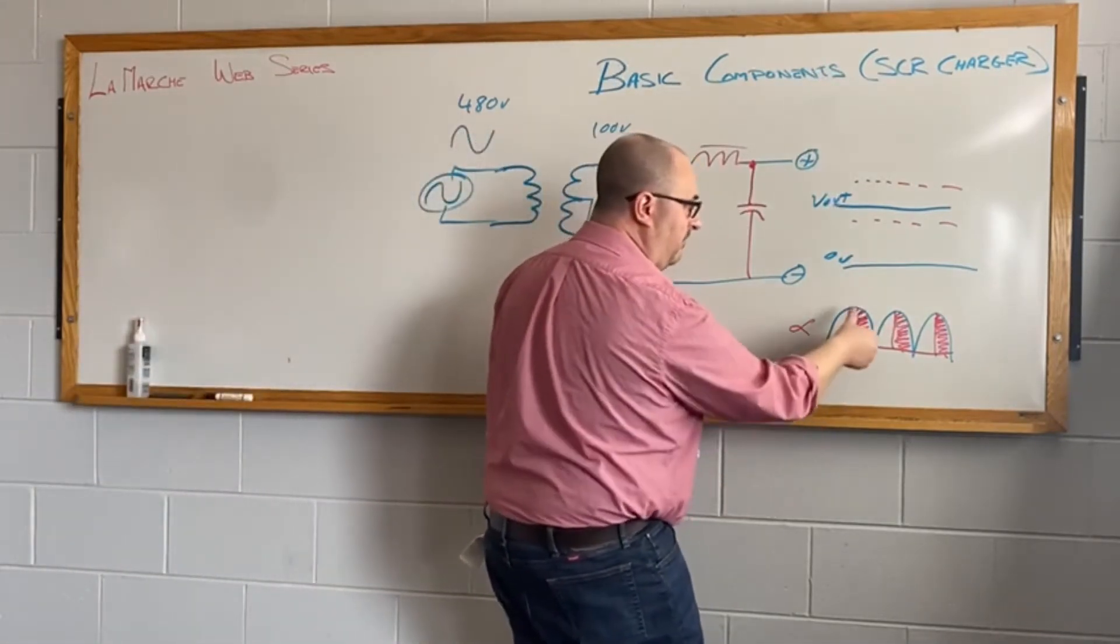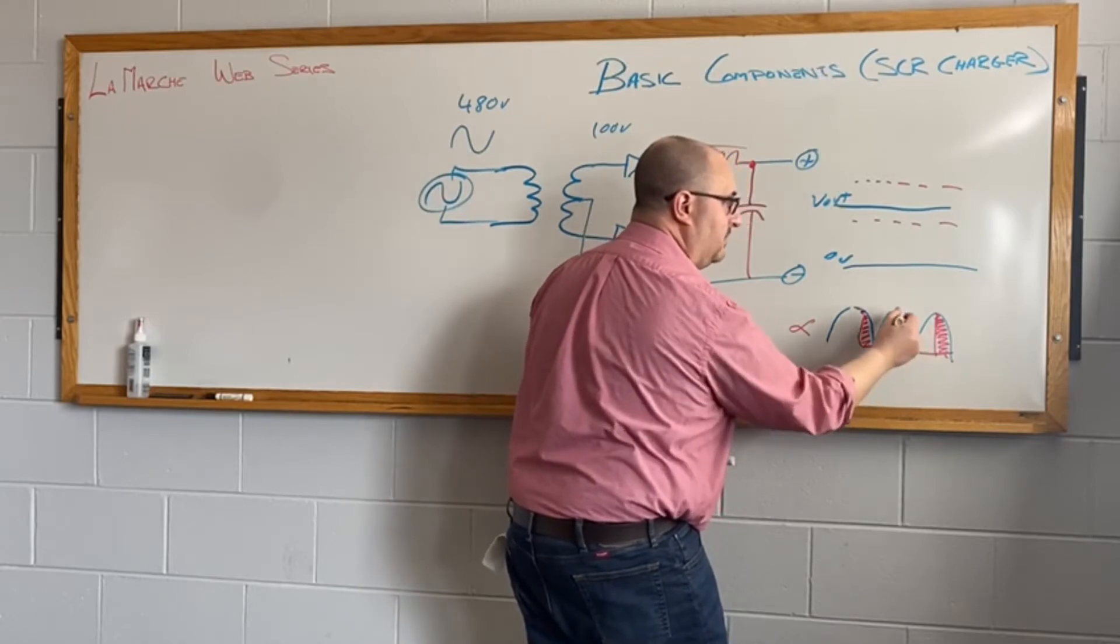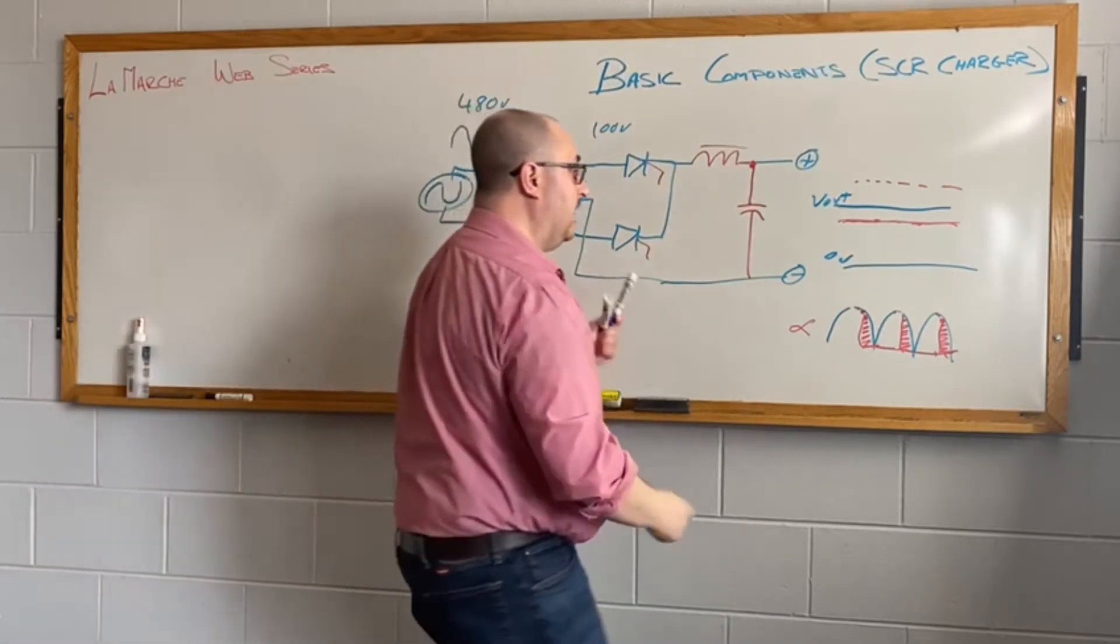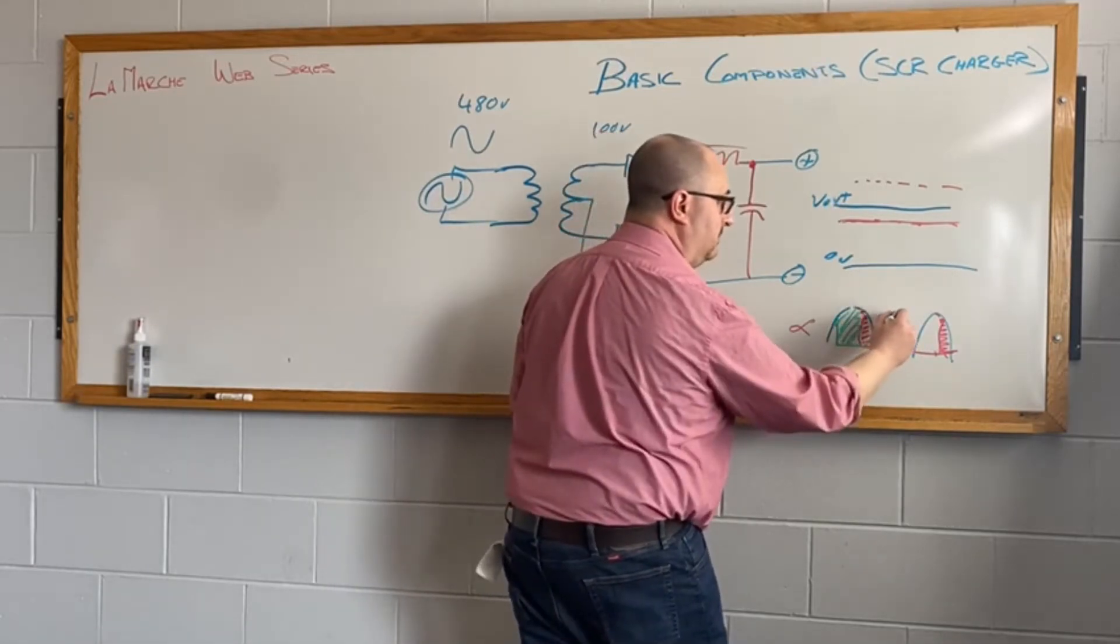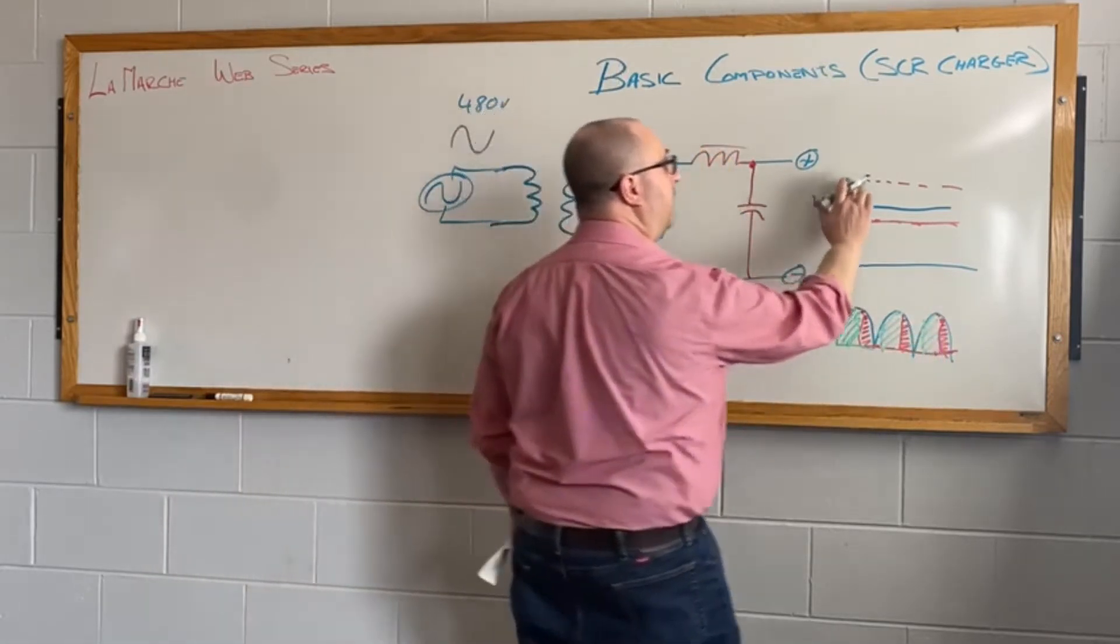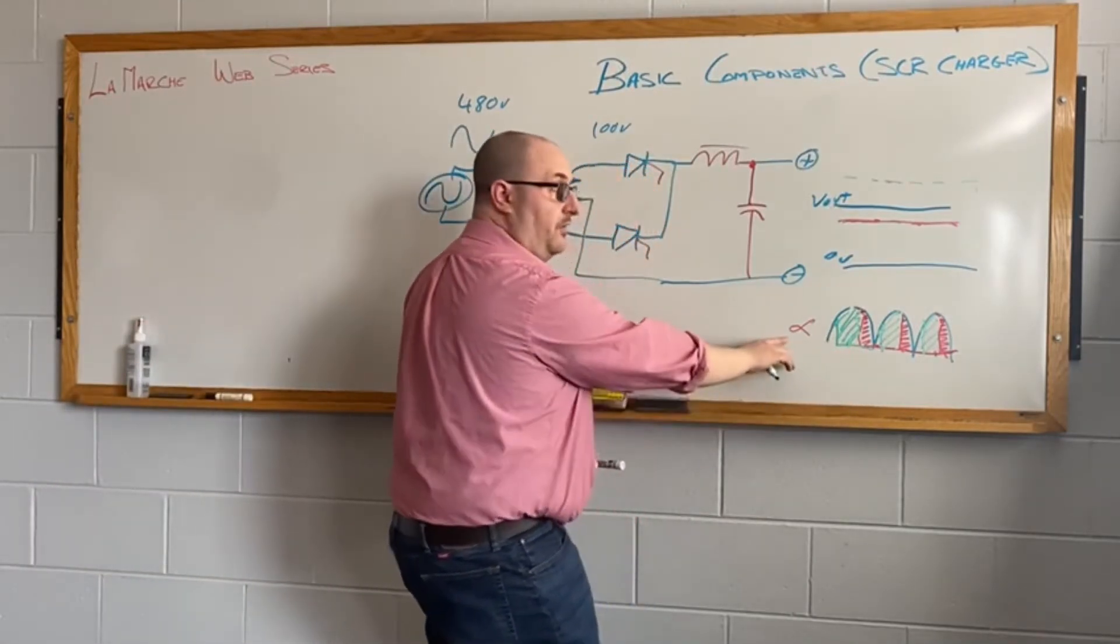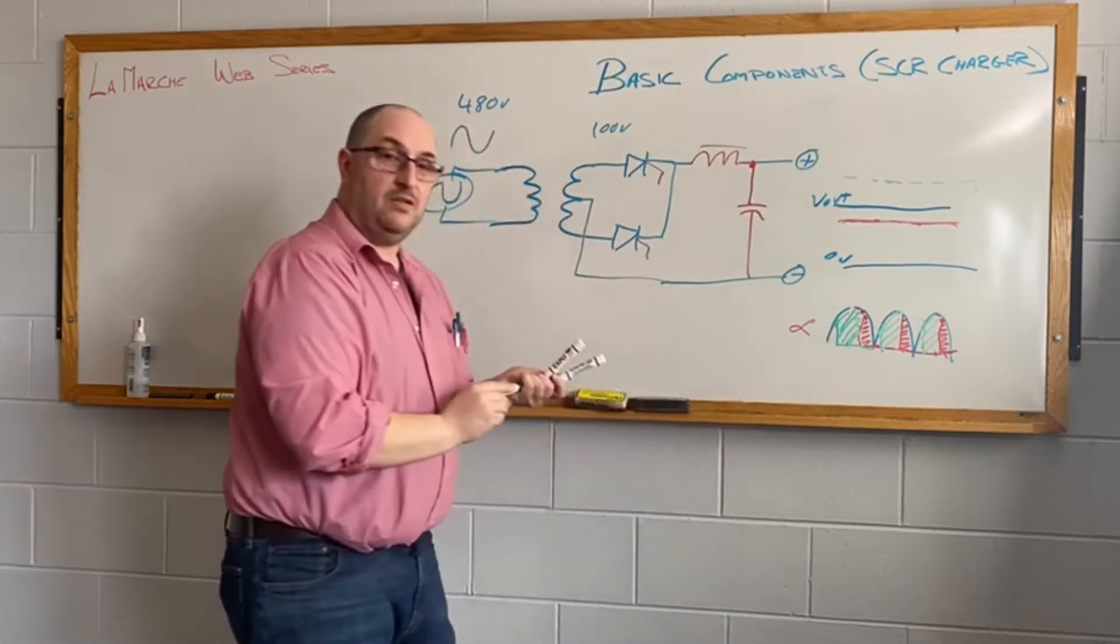What if this were my area? Very, very small percentage of it. Then I would be at this resulting lower voltage or lower current. What if I were to change and reduce my alpha such that I occupy the majority of this rectified sine wave? Well, that's actually going to result in a higher output. So you can see now how depending on the delay angle alpha that we fire the SCRs in the rectifier, we can directly control the output. So how's this actually done in practice?